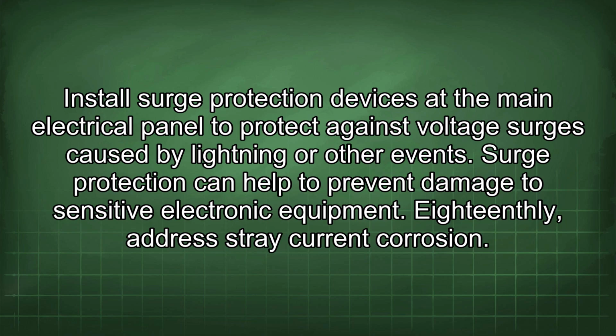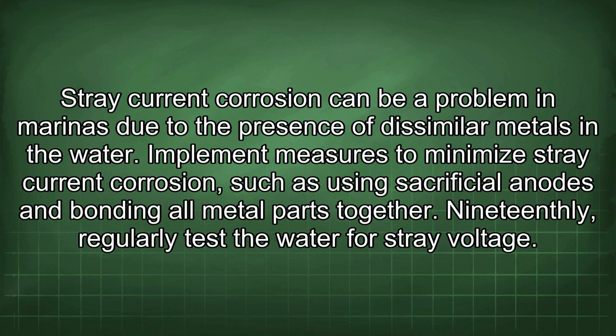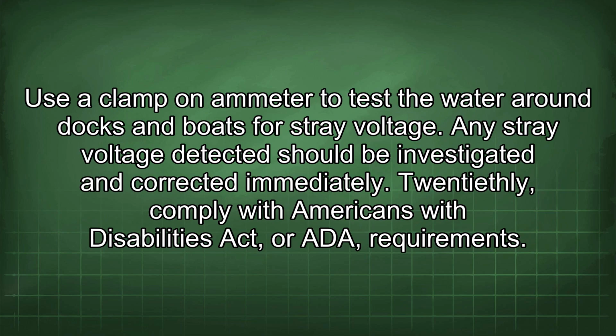18thly, address stray current corrosion. Stray current corrosion can be a problem in marinas due to the presence of dissimilar metals in the water. Implement measures to minimize stray current corrosion, such as using sacrificial anodes and bonding all metal parts together. 19thly, regularly test the water for stray voltage. Use a clamp-on ammeter to test the water around docks and boats for stray voltage. Any stray voltage detected should be investigated and corrected immediately.